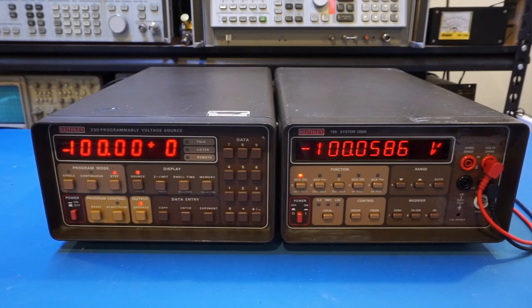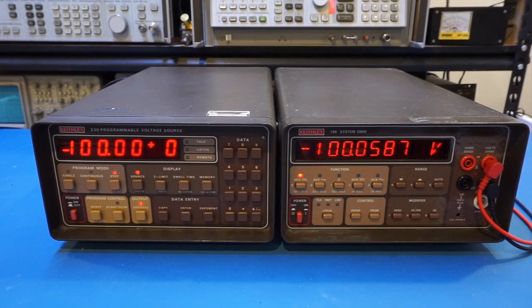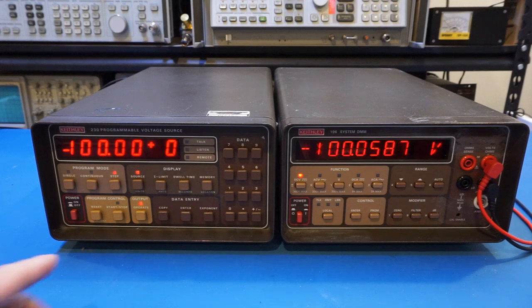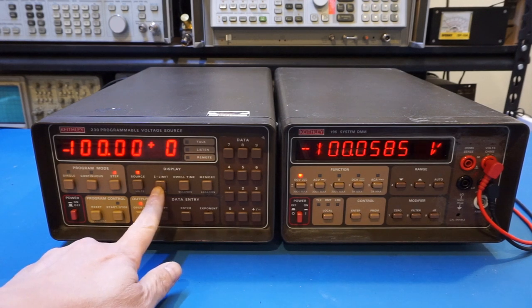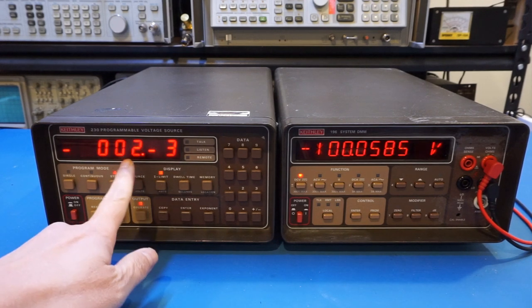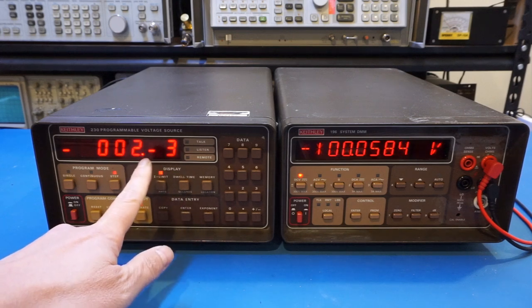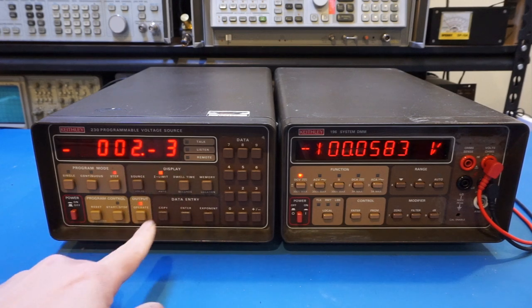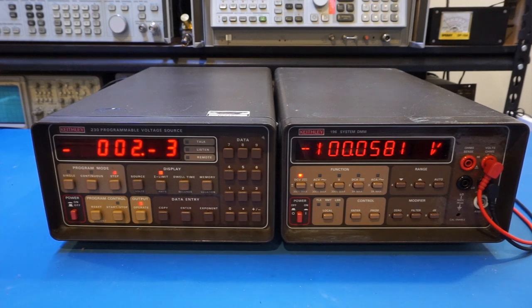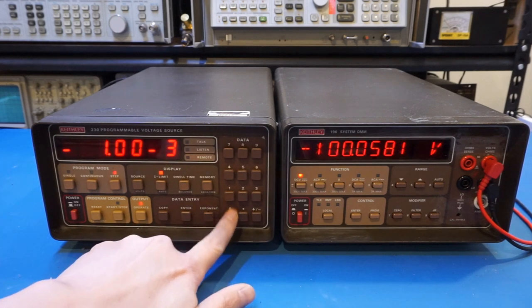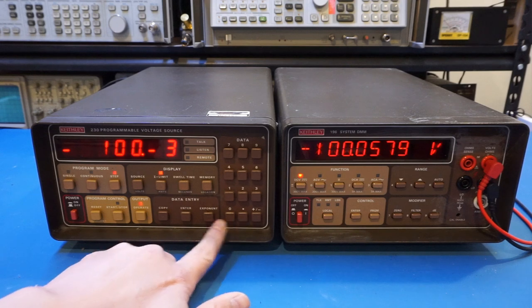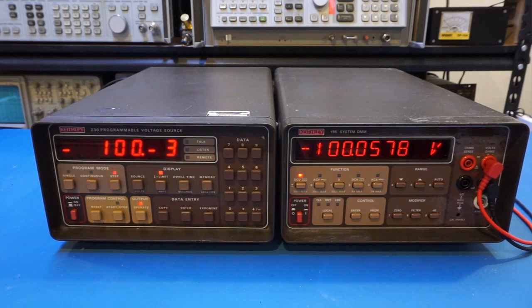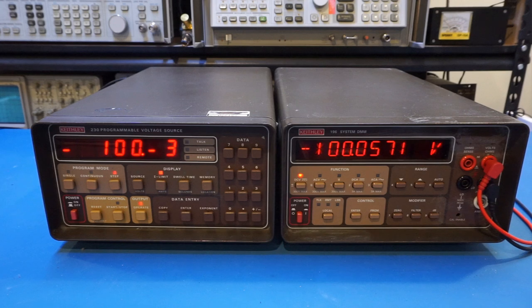Now, of course, we can set a lot of other parameters. For instance, we haven't really tried limiting the output current. And that is controlled by this I limit. So right now, it's set as 2 milliamps, right? So we can easily change that to 20 and 100 milliamp. For example, we can set it to 100 milliamp. And that would be your maximum output current.